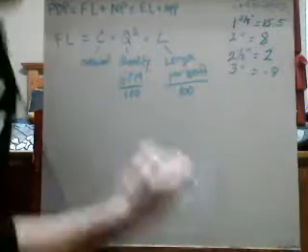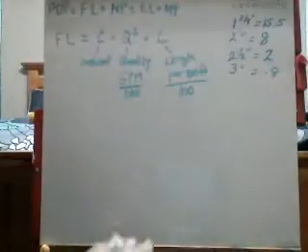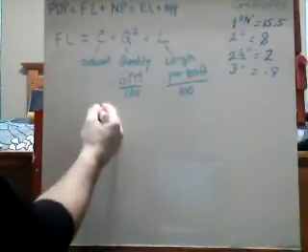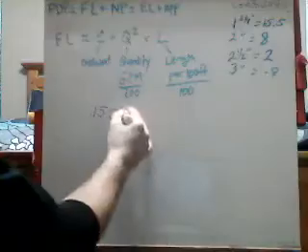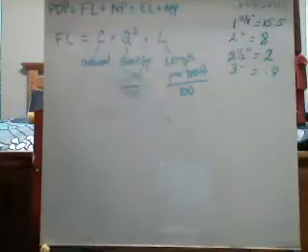So let's just figure we're going to be pumping just our regular 1 3/4 pre-connect. So it's 200 feet, right? What we want to do is plug in our coefficients, or everything that we know. What we know is your coefficient for 1 3/4 is 15.5. We'll skip the Q right now and go to length. We know the length is 200 feet, so it's 200.